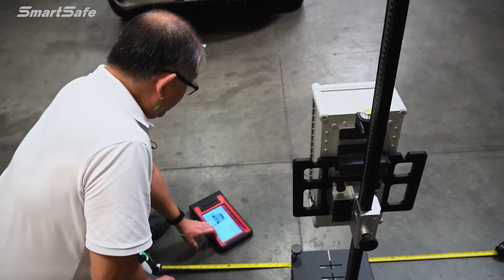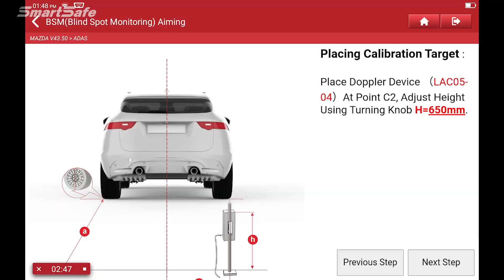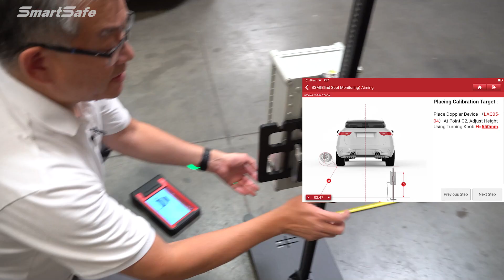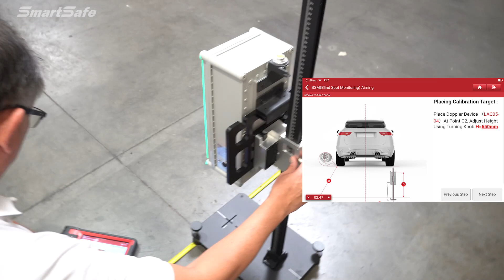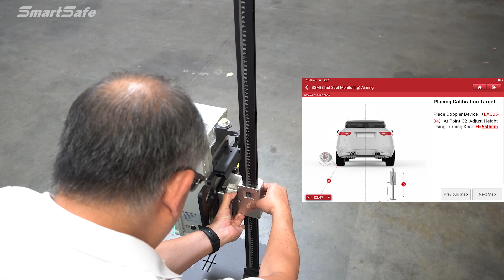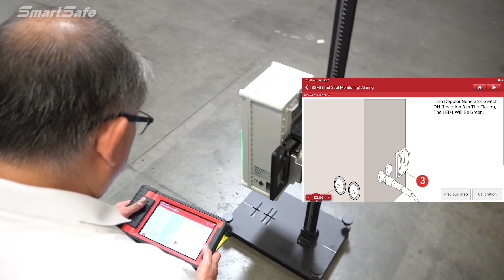And then the next step we'll have to do is adjust the height. So we're going to bring this up to 650 millimeters. Now when we're using the Doppler, this will be our marking point here. So I'm going to go ahead and lower this down to 650. And then we'll tighten that up. Let's make sure we're right on there. And we'll go ahead and move on to our next step.